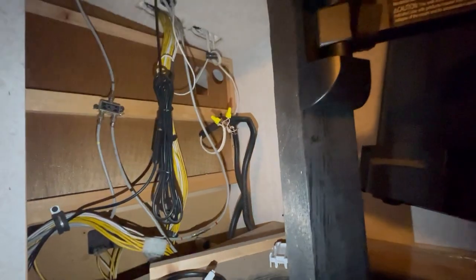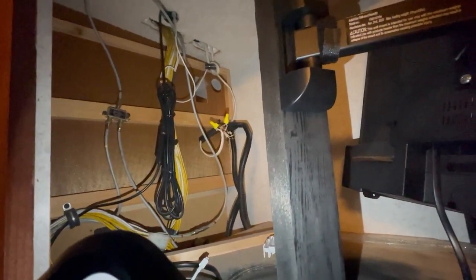And so what we found out when we got to testing was that there was a junction box back here. See if I can get my phone out here and get some light on the subject. There was a junction box. Now you can see where those connectors were at. There was actually a junction box right there. And so when we got to looking, we found out that the wire feed that was feeding that is bad. So we're gonna have to abandon that, because that is obviously in the wall, the way they run that, somewhere in this wall.